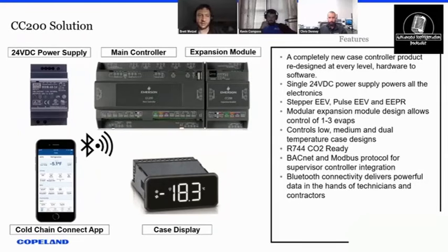One other question, because I'm not seeing it unless I'm just blind because I am getting older. Fuses. Are there any fuses? We do have one main power fuse, although I've yet to see one blow, but we do have one on the bottom left here that's a little glass fast blow fuse. So no, the evaporator contacts aren't fused, or the solenoid contacts. All the relays are Form C, and I can show the ratings if we get into the tech specs a little bit later. No, you're fine. Sorry.